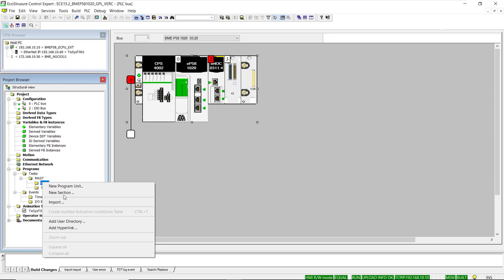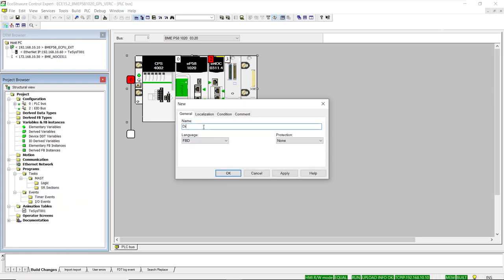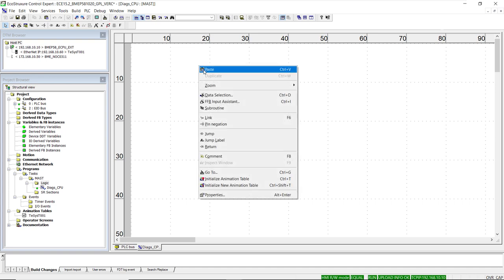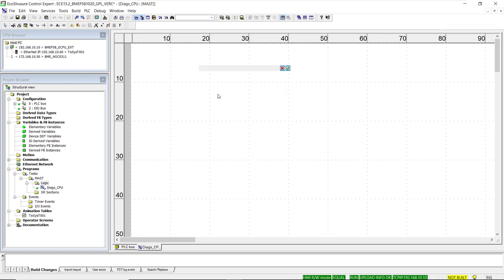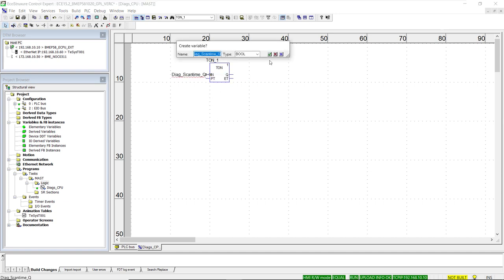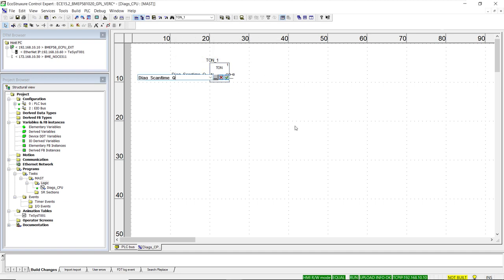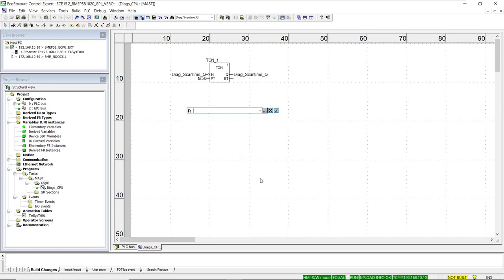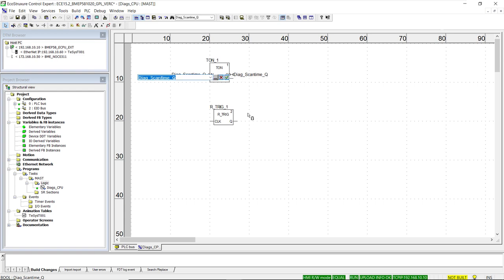We start by creating a new section called Diags CPU, which will include the client type function blocks to query information from the processor. Next, we add a timer to control the frequency at which the communication function blocks are triggered. Each time it reaches the preset time, it resets itself, which is why we negate the input to the timer, and we code a preset time of five seconds.